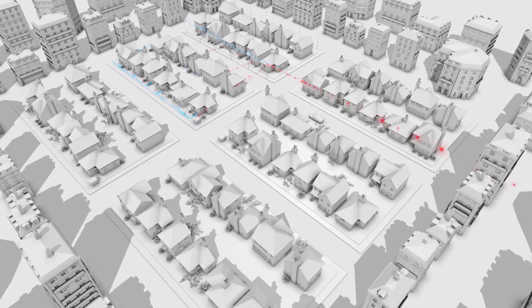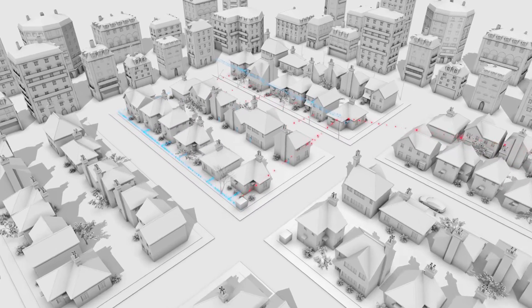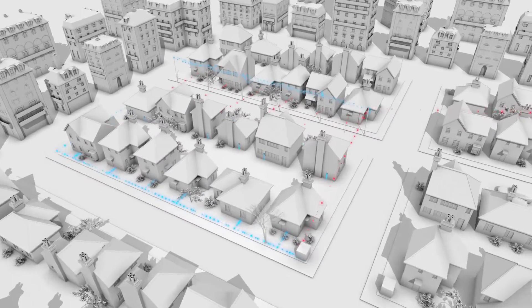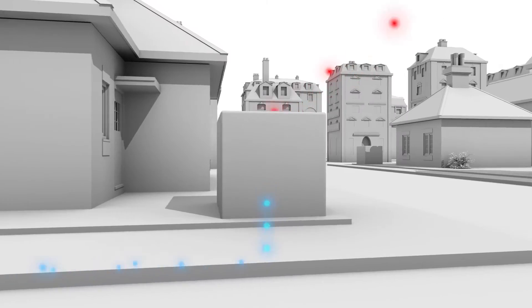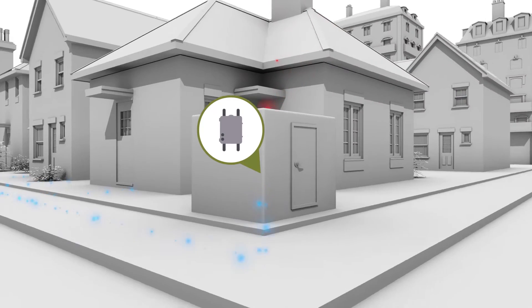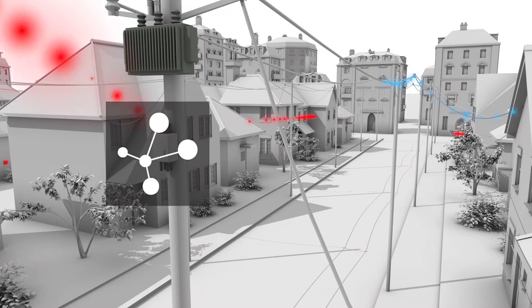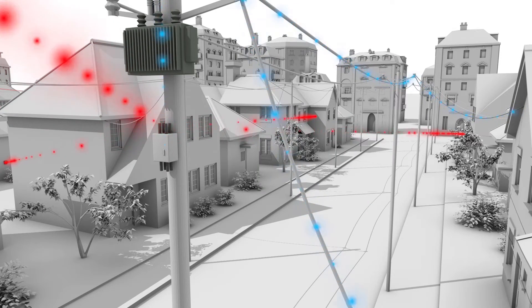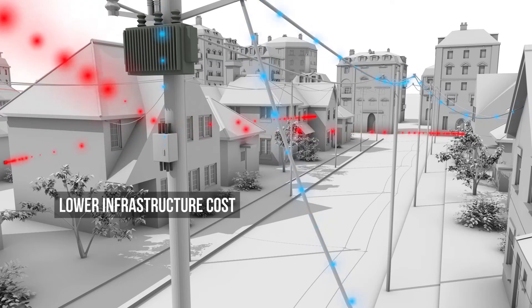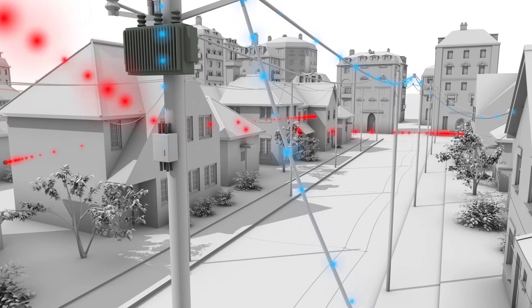In areas where there is a larger number of meters under each transformer, such as in many European cities, the traditional approach to meter communications has been to install a PLC data concentrator at every transformer. OpenWay Riva provides a more effective solution to deliver both cost and performance advantages. By combining RF mesh, PLC, and Wi-Fi communications in one solution, a single router serves a much larger number of meters, lowering infrastructure costs, backhaul costs, and adding network resiliency not available with current PLC-only solutions.